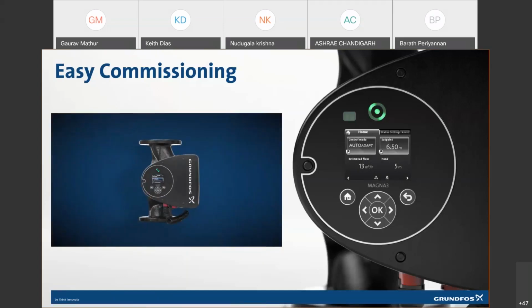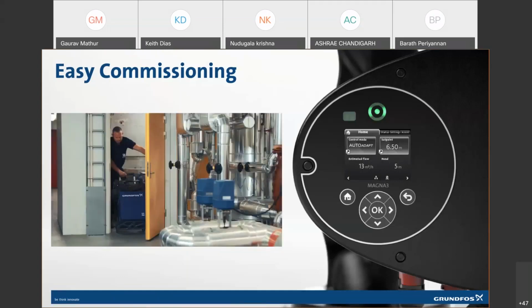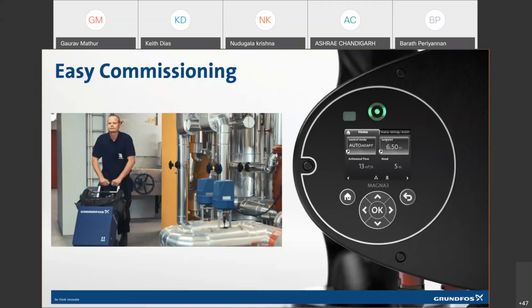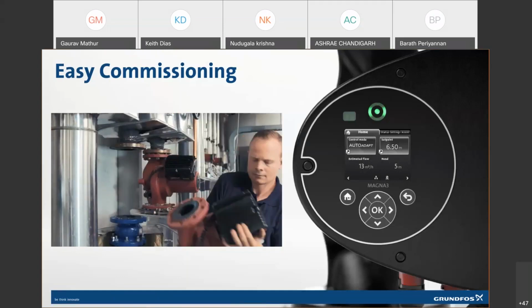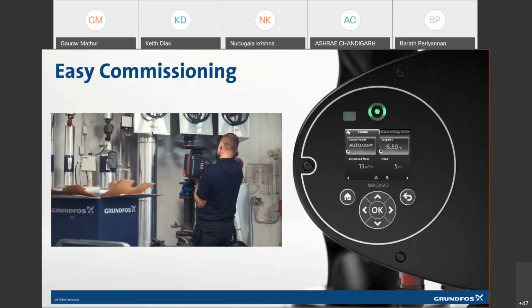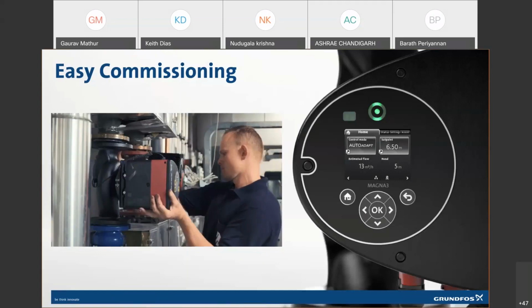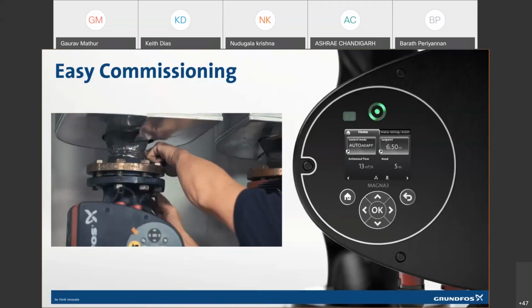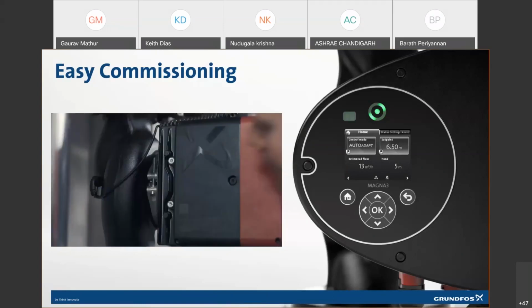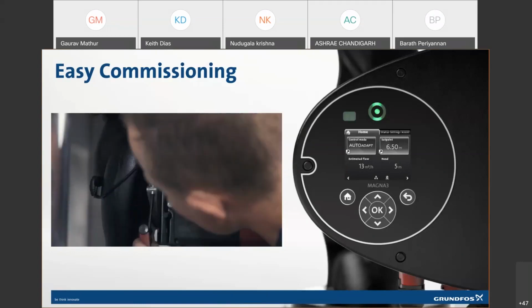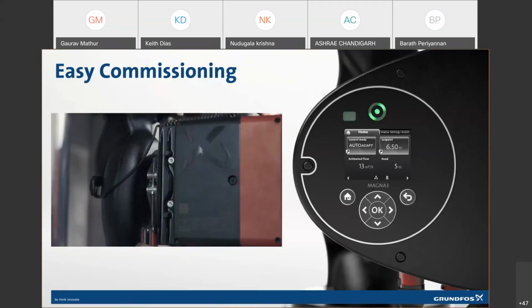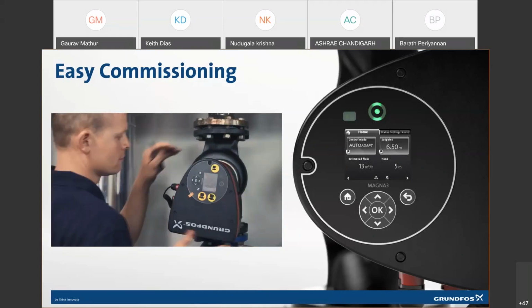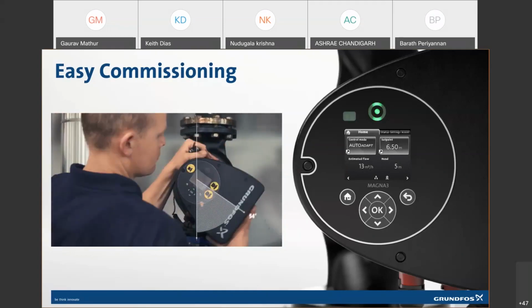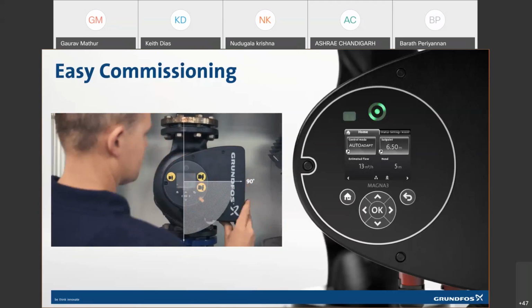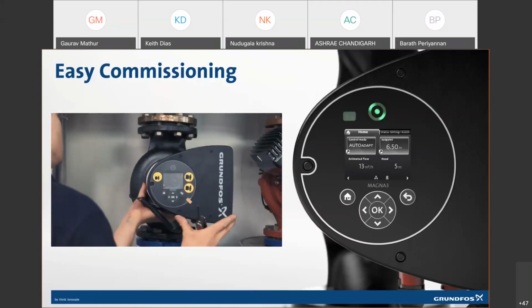Magna 3 is our state-of-the-art large circulator, and it's the pump you'll want to bring when your big customers ask for heating or cooling with world-class efficiency. Once you've got the Magna 3 firmly in place, start by simply loosening the new clamp ring screw so you can turn the pump head. The pump head must always be fixed in the 3 o'clock position, since the Magna 3 is air-cooled.